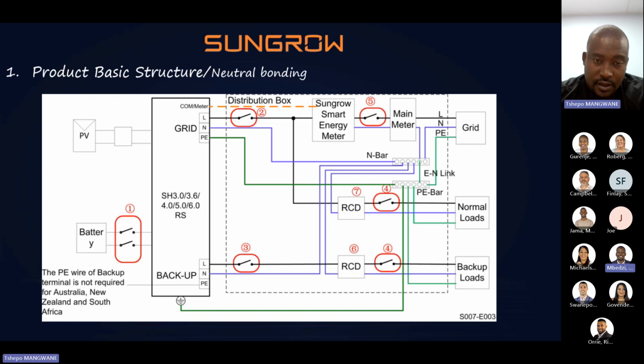When the grid is available, you don't need to put a contactor or relays to close it if the grid goes off. It needs to be bonded all the time. You can do it that way, but we prefer it to be a permanent bond. You can do it that way according to your municipality requirements, but most of them just do a permanent bond. It's common. So let's check on the drawing.